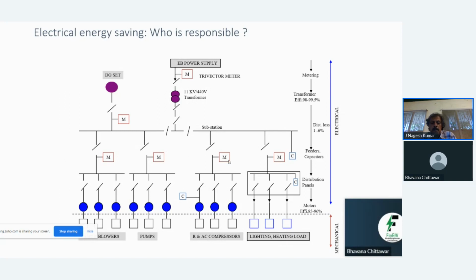This brings us to the question - which equipment consumes energy? Is it the motor? The motor itself does not need any energy. There is a driven equipment - a compressor, pump, or blower. The energy is demanded by the compressor. The motor simply supplies whatever is demanded by the compressor, and that energy demanded is supplied by the motor.